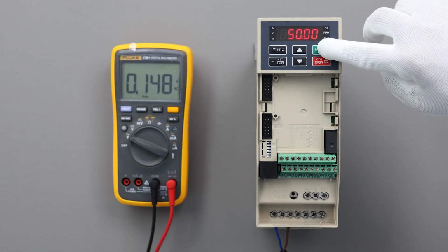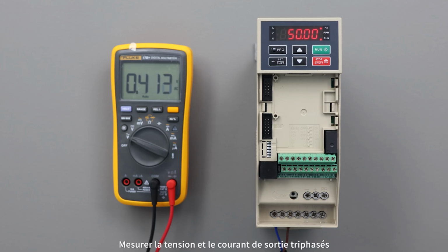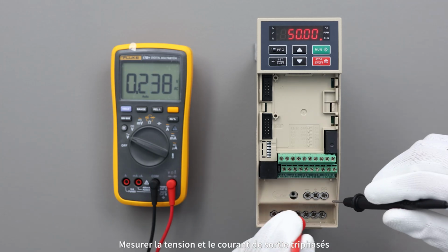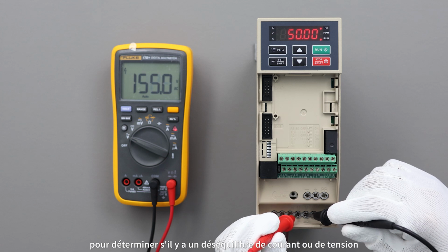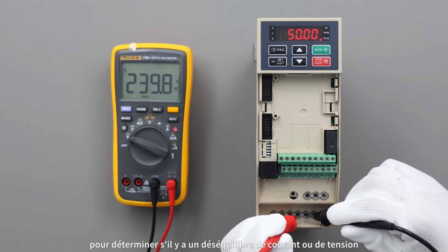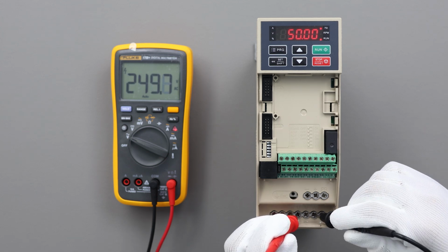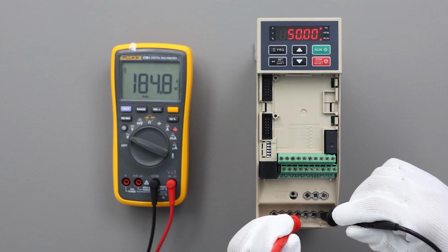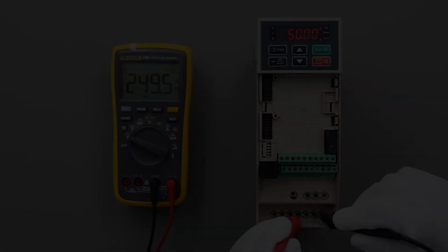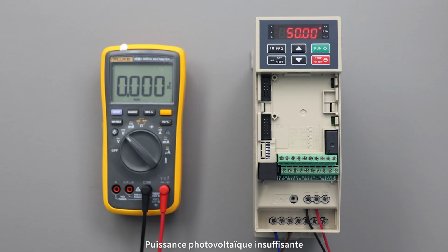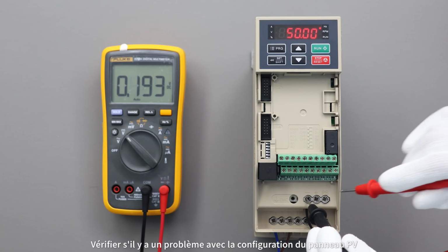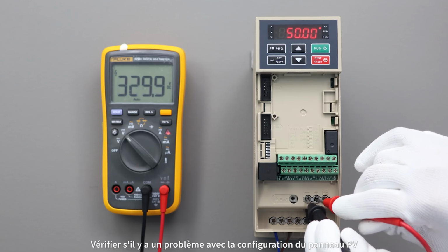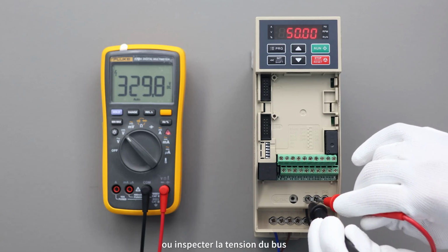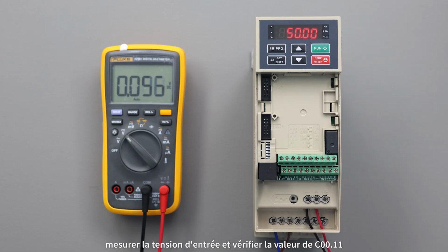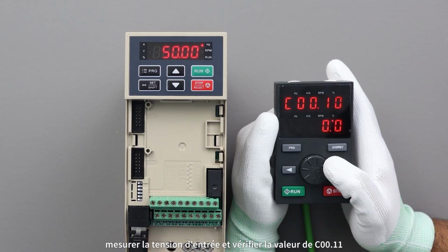Inspect three-phase output voltage and current. Measure the three-phase output voltage and current to identify if there is any unbalanced current or voltage. Insufficient PV power. Check if there is a problem with the PV panel configuration or inspect the bus voltage. Measure the input voltage and check the value of C00.11.